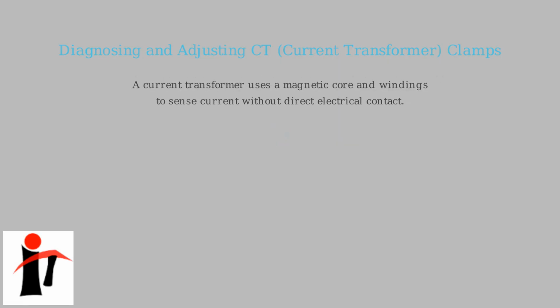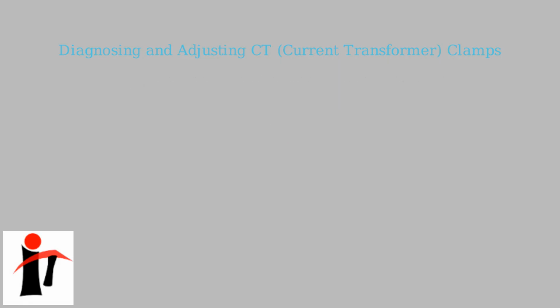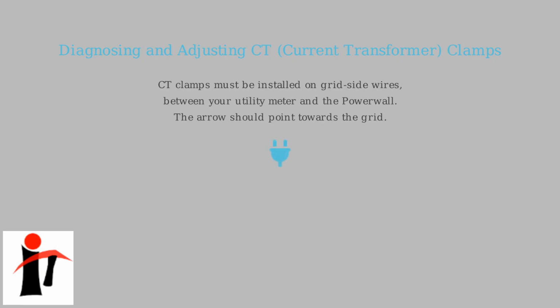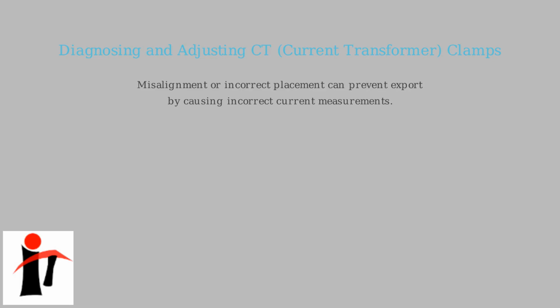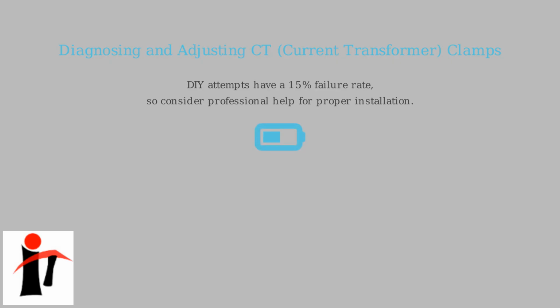CT clamps are crucial for measuring current flow and determining when to export energy. A current transformer uses a magnetic core and windings to sense current without direct electrical contact. They must be installed on the grid-side wires between your utility meter and the Powerwall, with the arrow pointing towards the grid. Misalignment or incorrect placement can prevent export by causing incorrect current measurements. Use the Tesla app or installer tools to guide you in repositioning the CTs for accurate current sensing. DIY attempts have a 15% failure rate, so consider professional help.